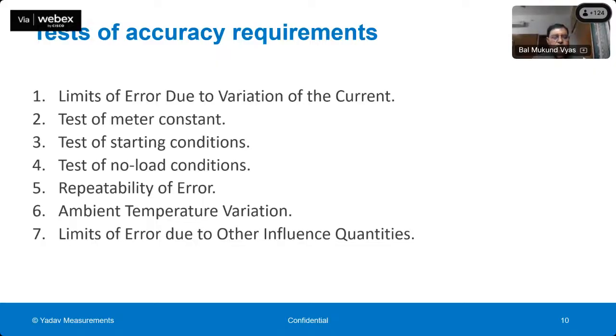Another very important test is the test of starting conditions. So the meter should start with some particular load. So that is the test of starting conditions, which are specified in the standard. Then there is a test of no load. No load means when all your loads are switched off, the meter should not record any energy. So that is a very important test which the meter has to pass. Then repeatability of error; the meter's error should be very repeatable. Ambient temperature influence. So when the temperature is varying, how much can the error of the meter vary? So that's ambient temperature variation. And limits of error due to other influence quantities. There are about 12 to 13 influence quantities which can influence the accuracy of the meters. So the meter has to undergo all these tests.